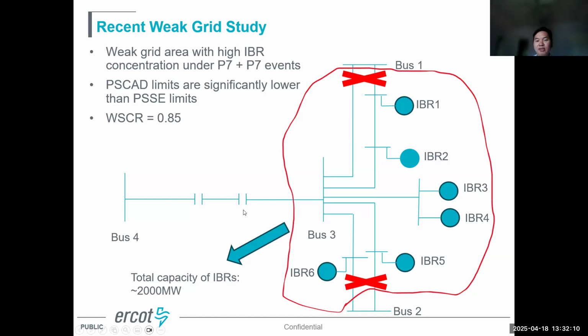But in this one, it's not really an SSI issue. The series compensation here actually helps the stability performance. So if we bypass the series compensation, the performance is actually worse. Which indicates the issue here is really system strength. And we calculate WSCR, the value is only 0.85.